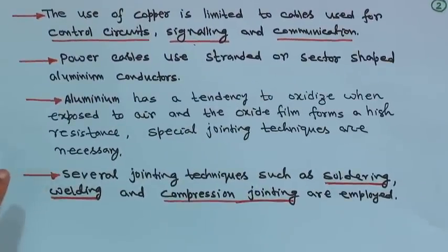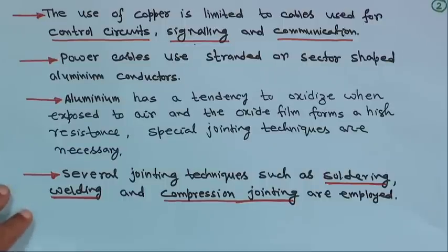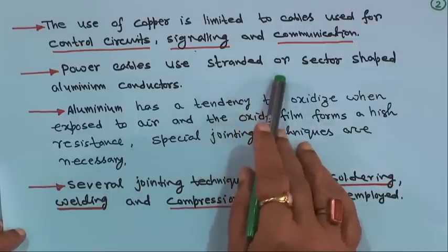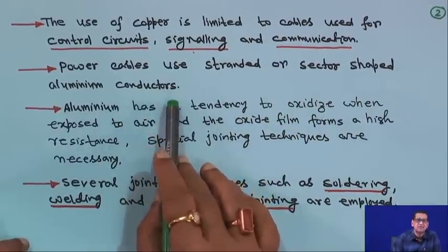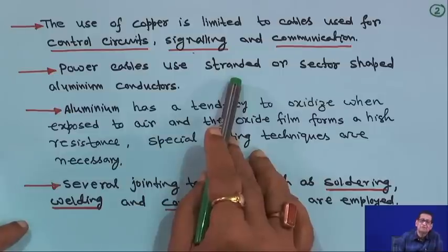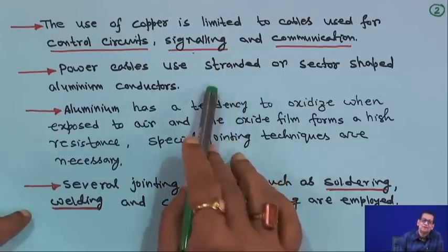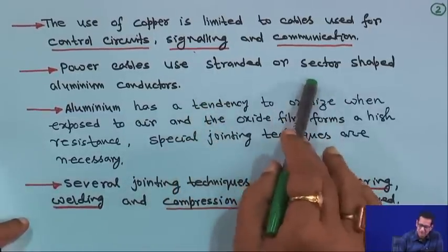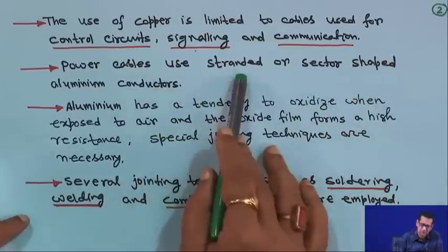The materials employed for conductors are generally annealed copper or aluminium. The use of copper is limited to cables used for control circuits, signaling, and communication. Aluminium is used for power cables — either stranded or sector-shaped aluminium conductors. Aluminium has a tendency to oxidize when exposed to air, forming an oxide film of very high resistance.